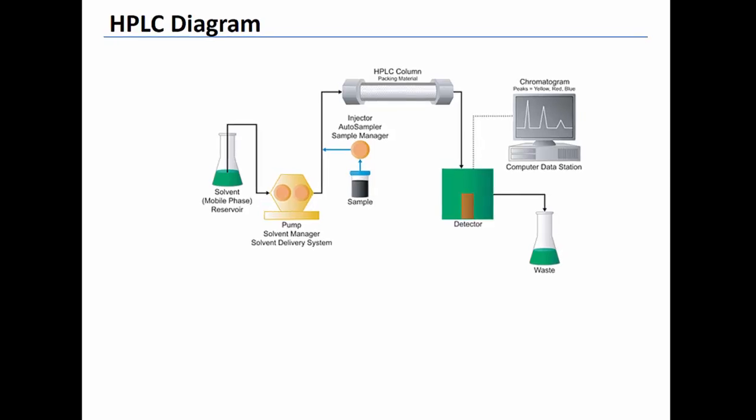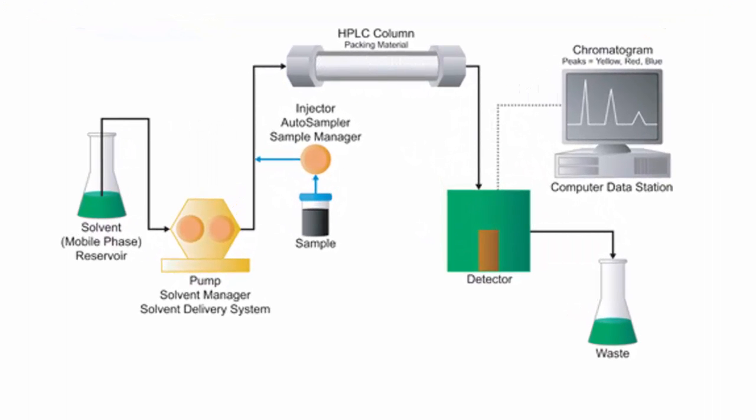The diagram shown on the screen is a schematic of the important components of an HPLC. At the beginning of the diagram are one or more solvents, which are pressurized by a pump. The solvents make up what is called the mobile phase. A small volume of sample is injected into the pressurized mobile phase. The flow of the mobile phase then carries the sample to the HPLC column, where ideally all analytes of interest are separated.